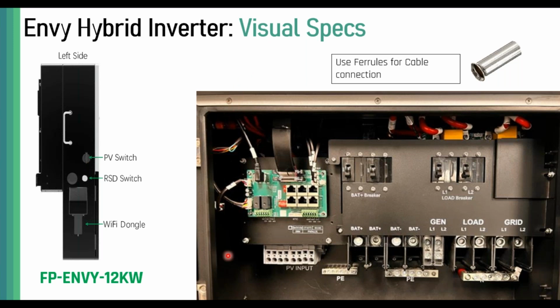Then we're moving inside of the inverter. Moving inside, we have first the communication board. The communication board serves to communicate both the inverter with the battery for closed loop, and inverter to inverter when you're paralleling up to 5 units as mentioned. It also provides a USB port. As it is a new product, and as we come up with better applications and better settings, we can locally update the LCD by just plugging in a USB with some simple step-by-step processes. It takes about 5 minutes to upload the software into the inverter, and then you have some new settings.